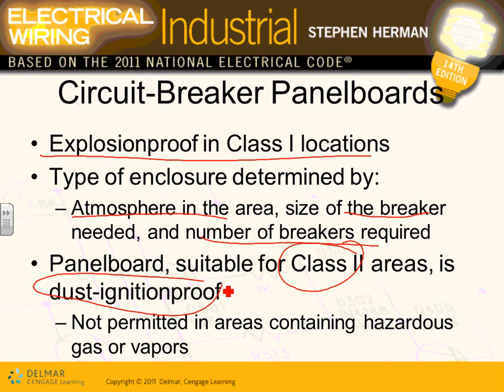The most expensive one is going to be the explosion-proof equipment. The second most expensive is the dust ignition-proof. The third one is called dust tight. Dust tight, guys, is just sealed a little bit so that the dust cannot get into it. That's all. It could ignite the surroundings, but not the dust. So explosion-proof is the most expensive, dust ignition-proof the second, and dust tight the third in terms of how much you pay. But you can't put dust tight in a Class 2 Div 1. You have to have dust ignition proof in a Class 2 Div 1. So there are certain locations. Long story short, if you have explosion-proof equipment, man, you're good for most of these locations.